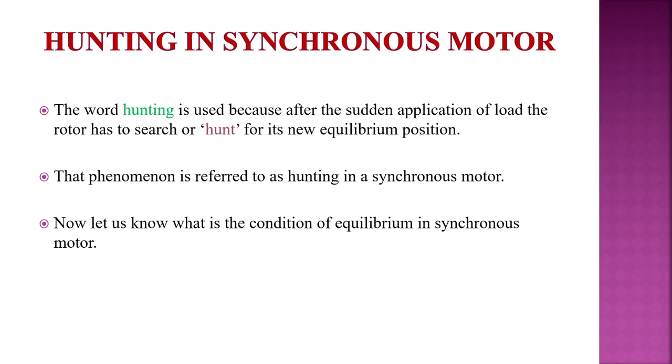The most significant adverse effect of hunting is increase in probability of losing synchronism. Hunting will also produce severe mechanical stresses as well as large variations in current and power drawn by the motor. Other effects can be increase in losses, which will result in increase of temperature, and increase in possibility of resonance.